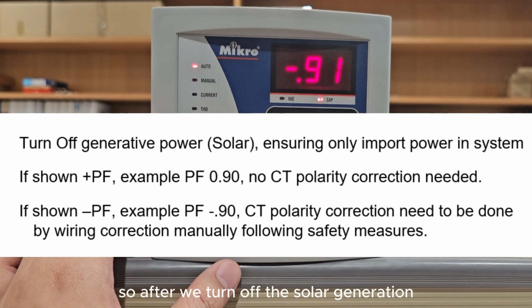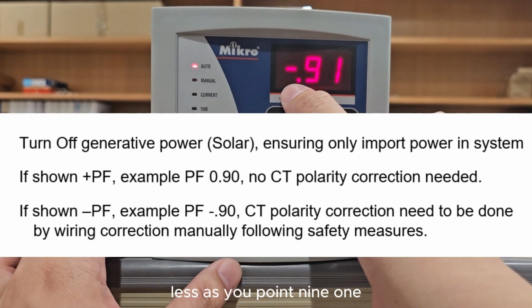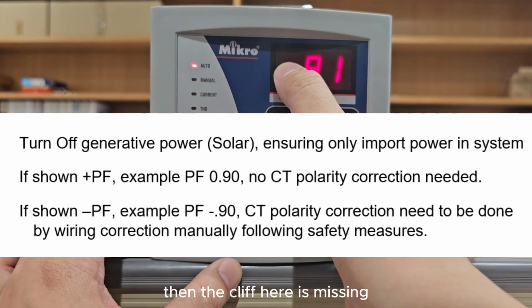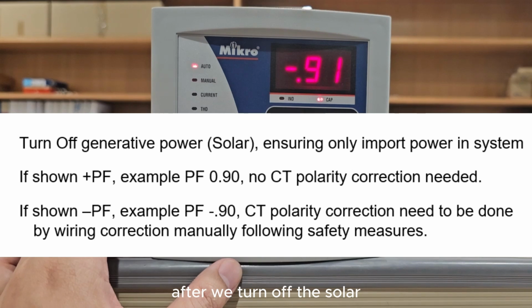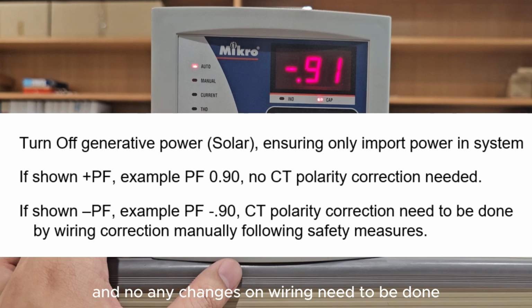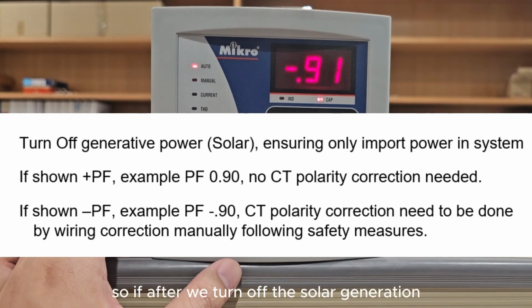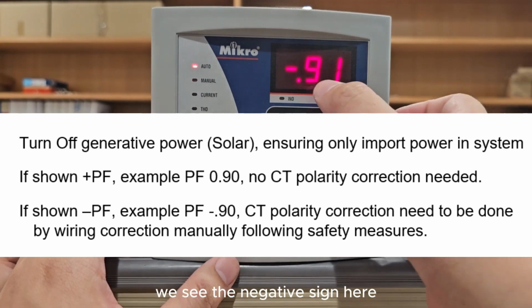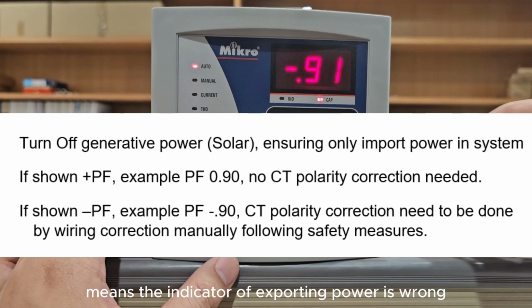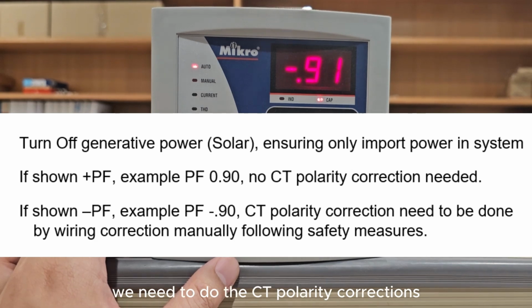So after we turn off the solar generation, if we see the positive sign here, let's say 0.91, the negative sign is missing, it means the polarity is already correct and no changes on wiring need to be done. But if after we turn off the solar generation, we see the negative sign here, negative 0.91, it means the indication of export and import power is wrong. We need to do the CT polarity corrections.